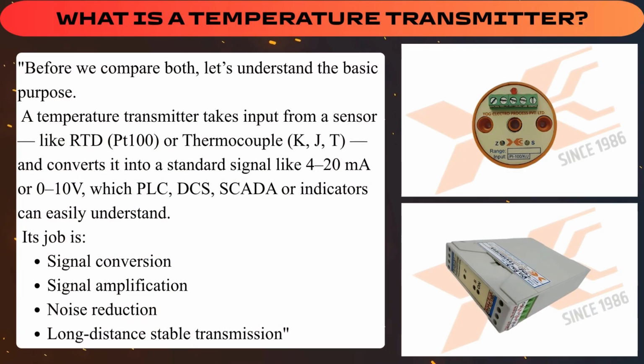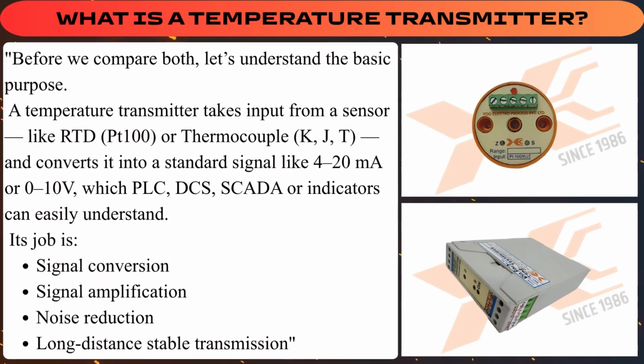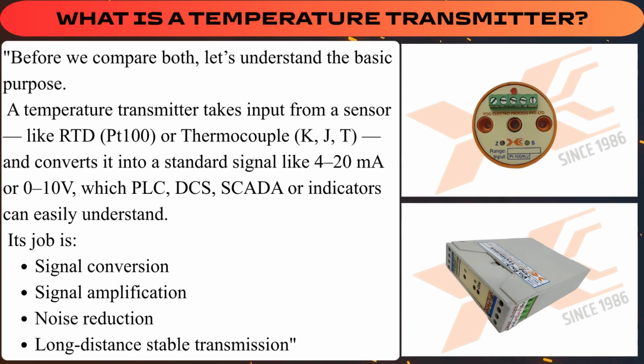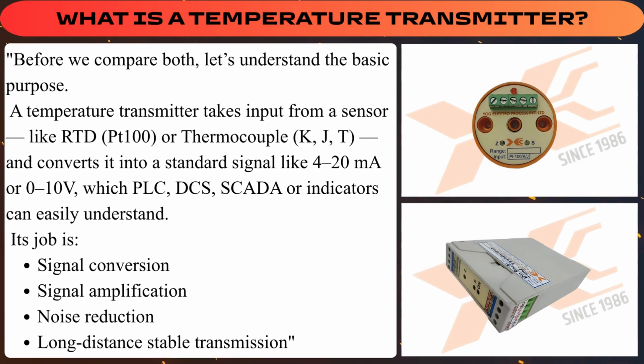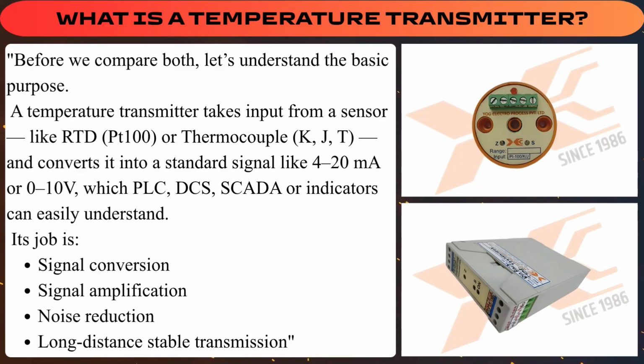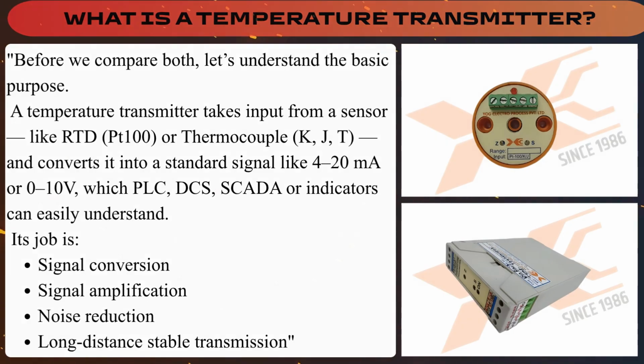What is a temperature transmitter? Before we compare both, let's understand the basic purpose. A temperature transmitter takes input from a sensor like RTD, PT100 or thermocouple KJT and converts it into a standard signal like 4 to 20 milliampere or 0 to 10 volt, which PLC, DCS, SCADA or indicators can easily understand. Its job is signal conversion, signal amplification, noise reduction, long-distance stable transmission.